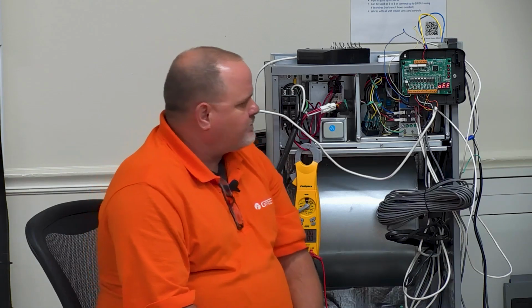Make sure, if you're wanting to have an air cleaner type filter, that's not done on a 1-inch filter. You need to be using like a 4-inch filter that's got plenty of media. Every filter out there has a static pressure drop rating across it, and using too thick of a filter, you're going to get too much static pressure drop across it, and it's going to cause you airflow problems. It can cause you airflow problems even when it's clean. So then once you get the filter dirty, now it's even going to be more of a problem. So keep all that in mind when you're setting these things up.